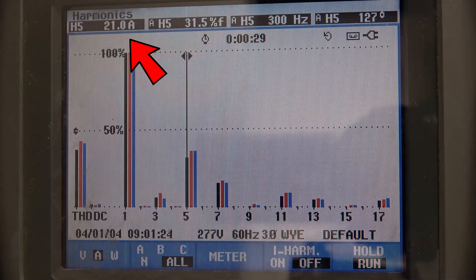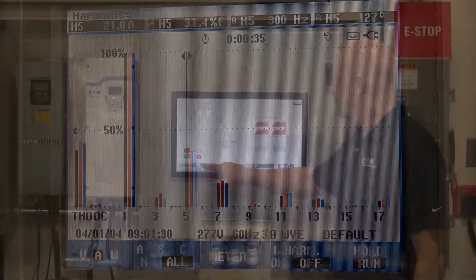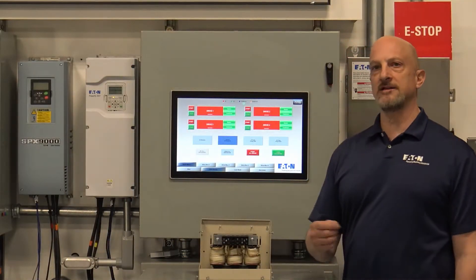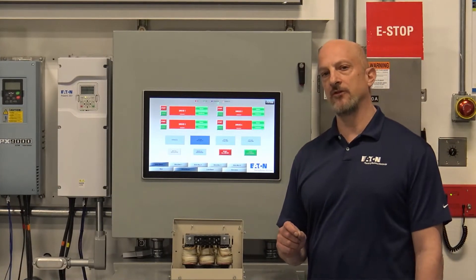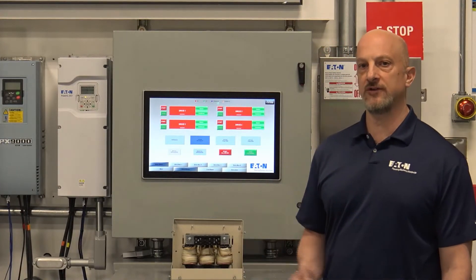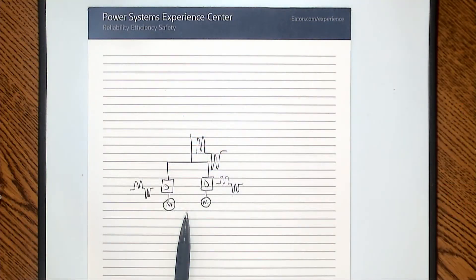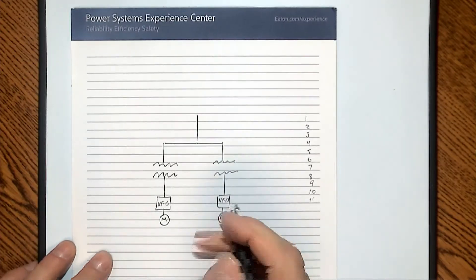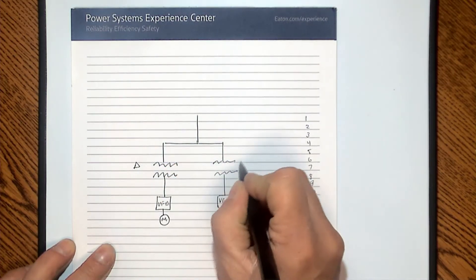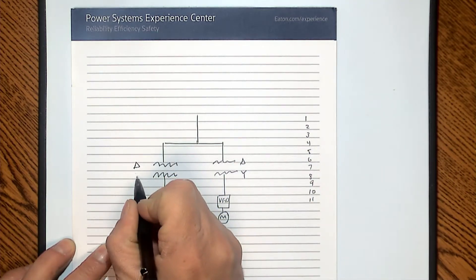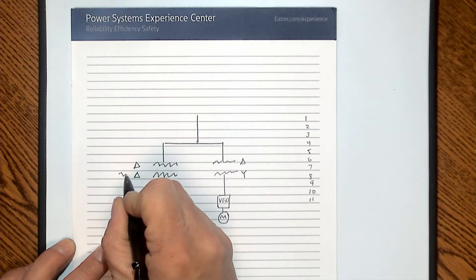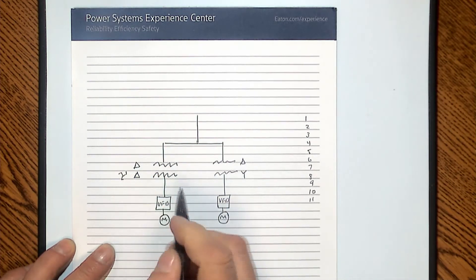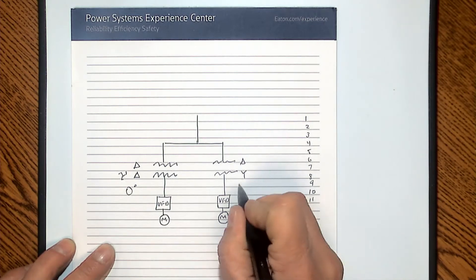Now we're going to turn those drives off and go back to the paper to describe what happens when we put two drives on but with phase-shifting transformers. With phase-shifting transformers, we have a situation where we put, for example, a delta-Y on one side and a delta-delta or delta-zigzag on the other side — which effectively gives you a zero degree phase shift on one and 30 degrees on the other.